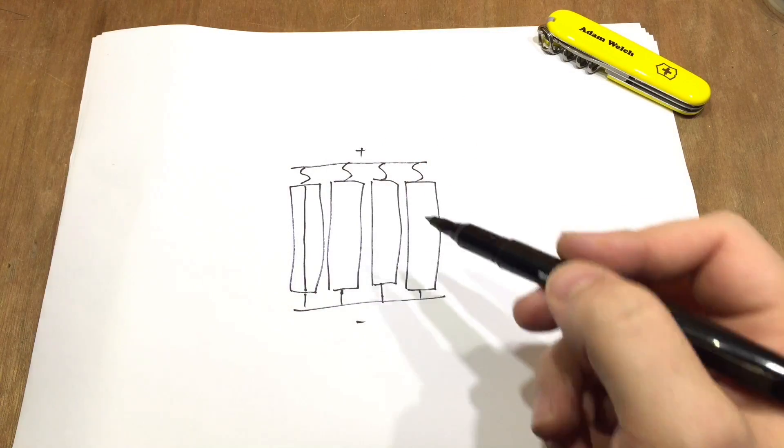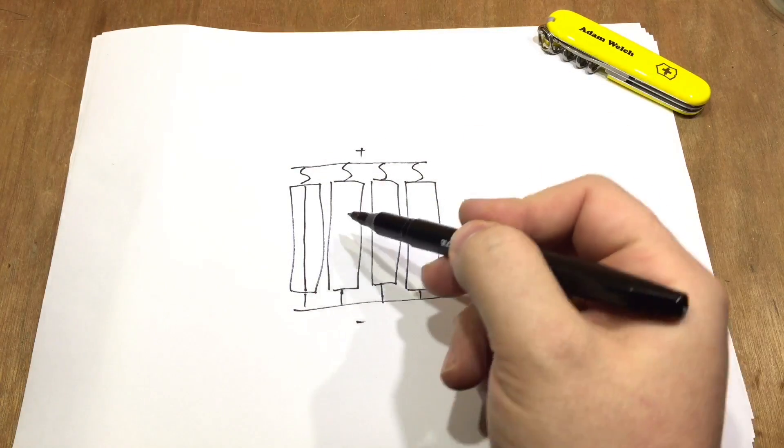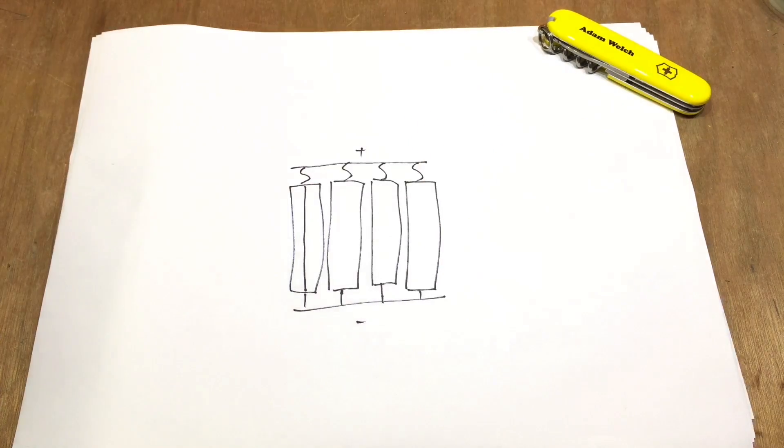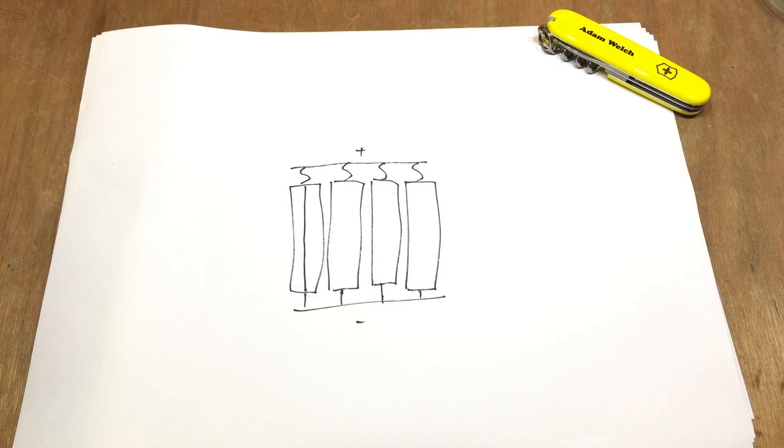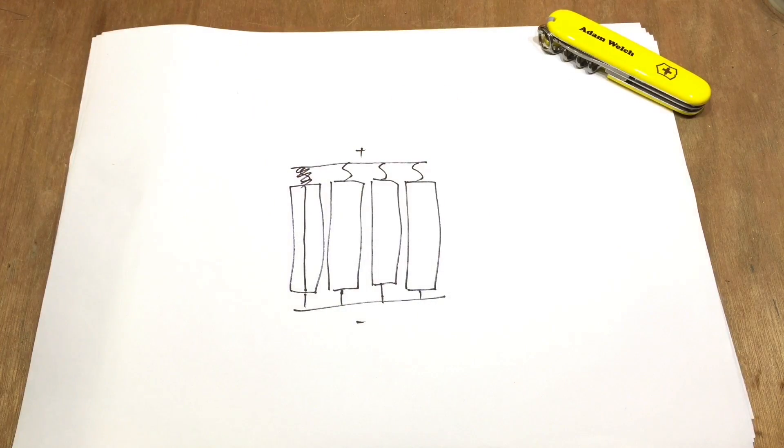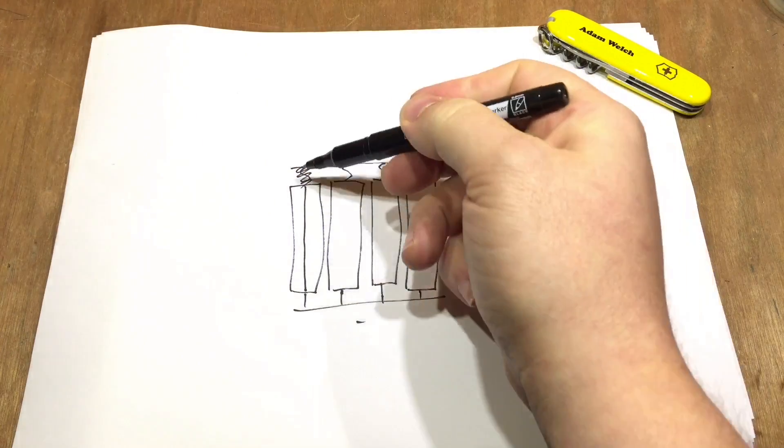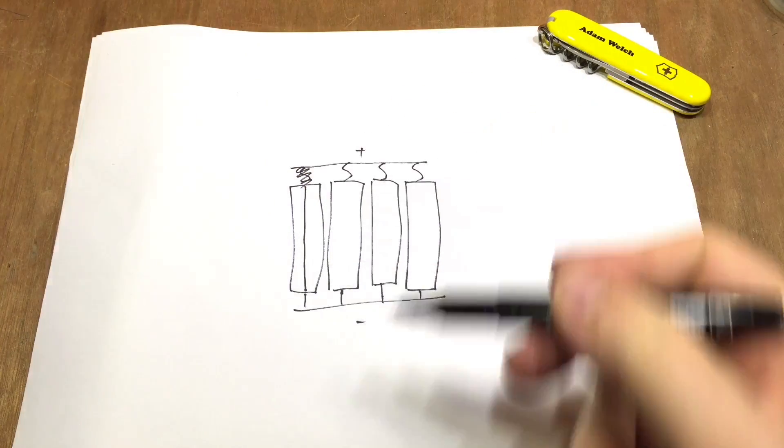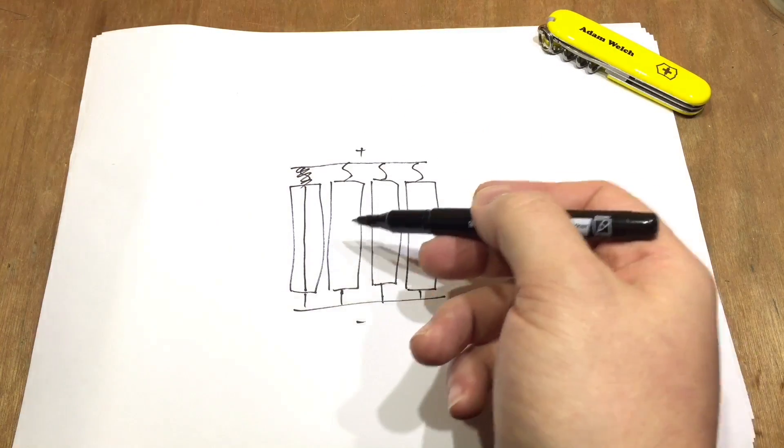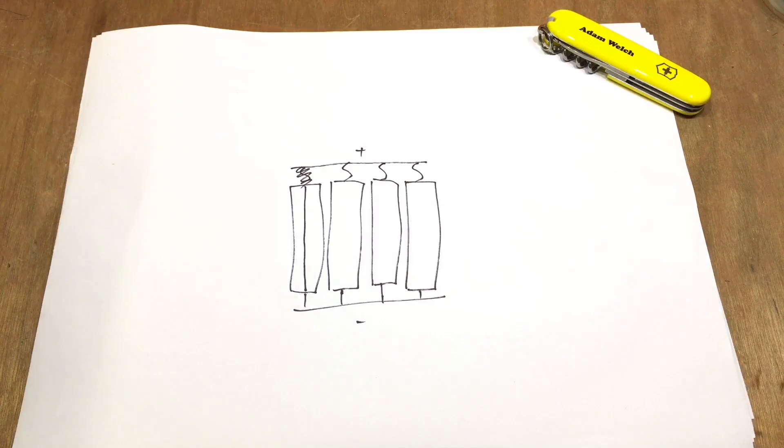So in that case, when these three start to deliver a lot of current through this dodgy cell here, hopefully that will fuse the fuse and take this cell out of the circuit and the remaining cells will carry on as normal.